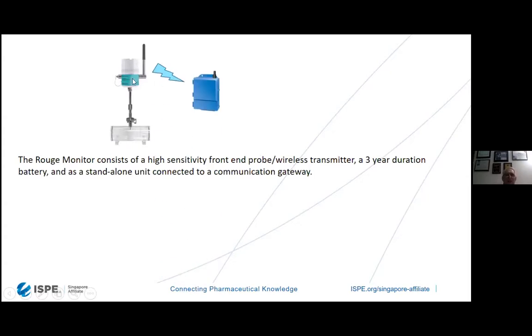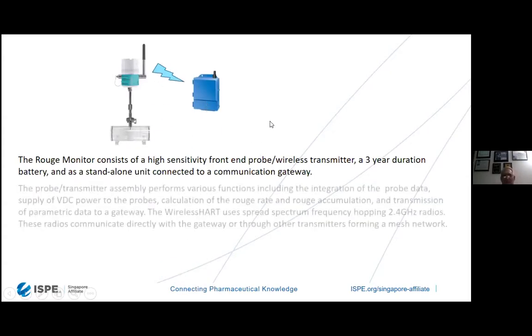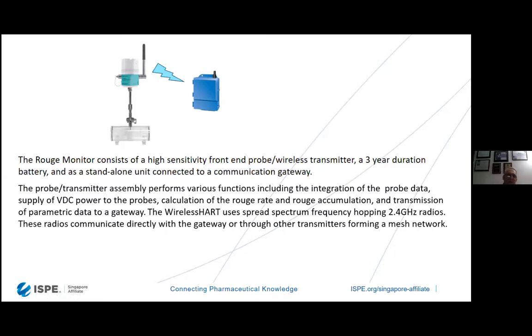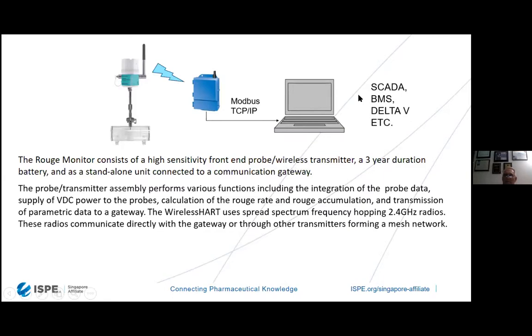The gateway then processes that information and uses it to transmit the information through Modbus or whatever over to a computer system or to a data display or data distribution system, a building management system, SCADA or whatever. So the system over here sends this by wireless radio over to the gateway, it's processed in the gateway, sent over by Modbus over to the computer system, including Delta V, BMS, SCADA, whatever it might be that you're using.